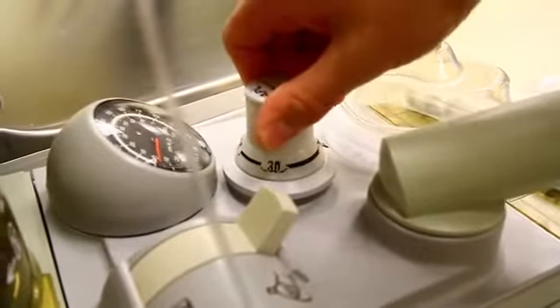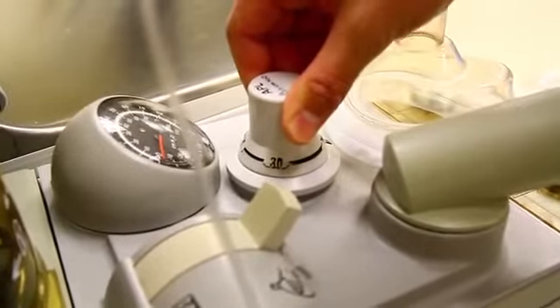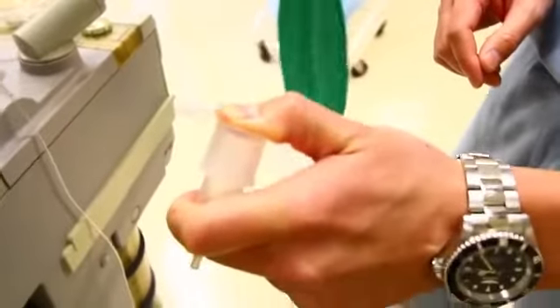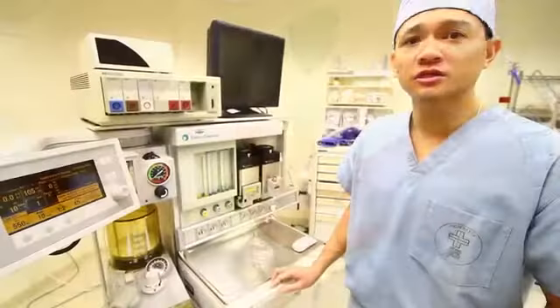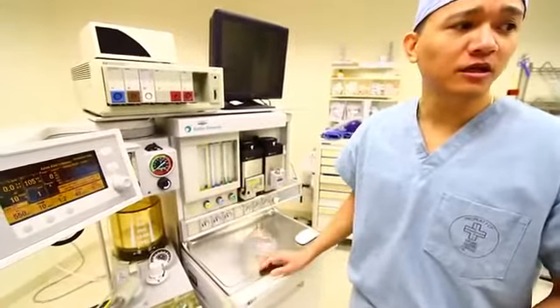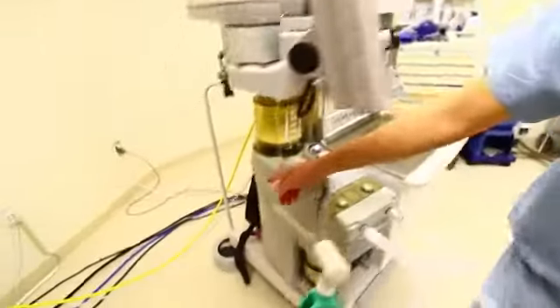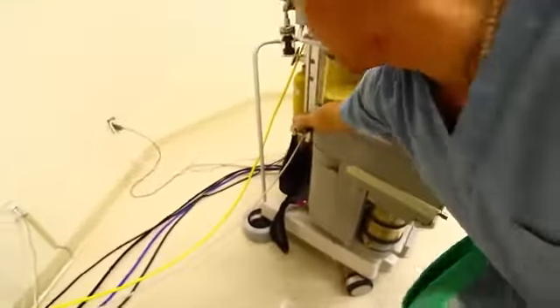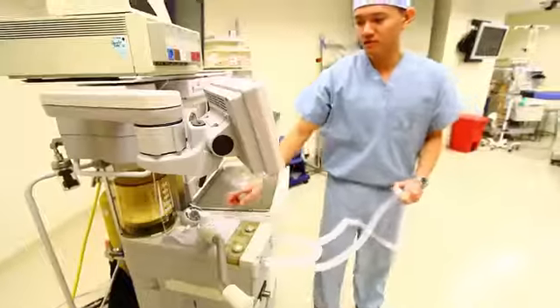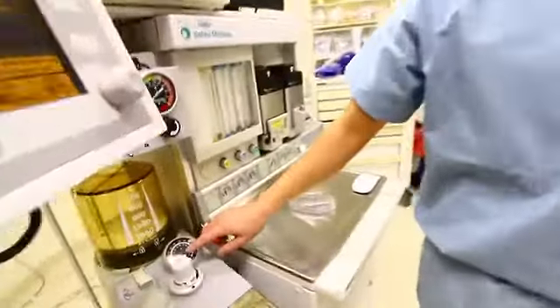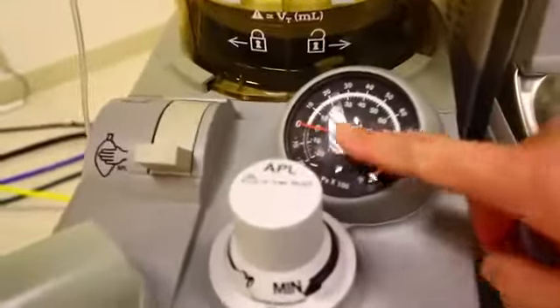Now fully open the APL or pop-off valve. Then occlude the Y piece. So with minimum oxygen flow, allow the scavenger reservoir bag to collapse completely. Note on your pressure gauge that it doesn't drop below 0.